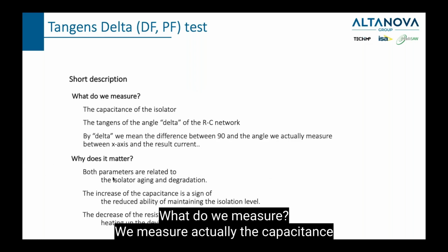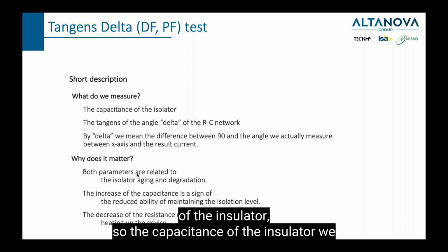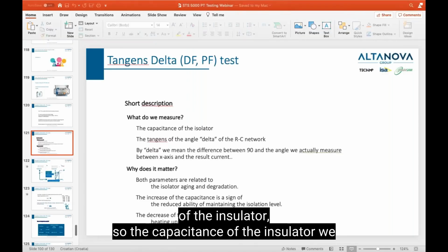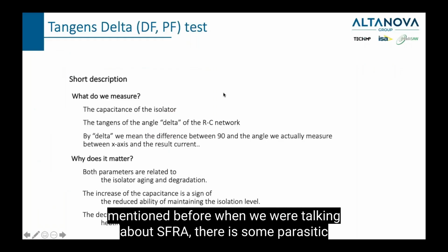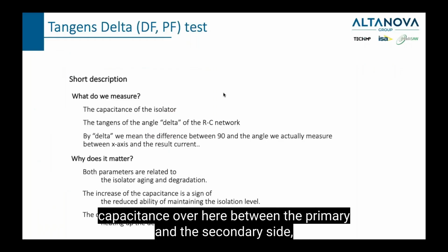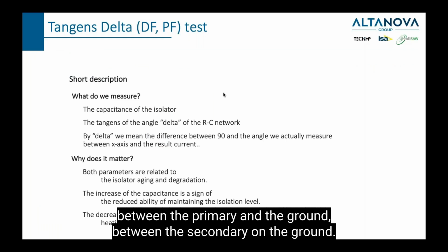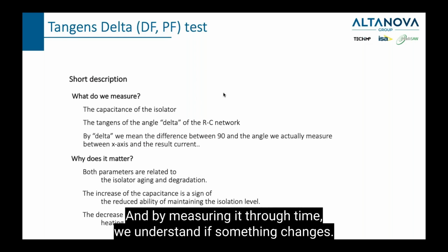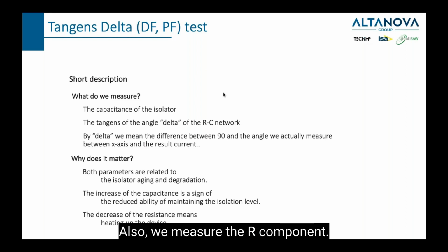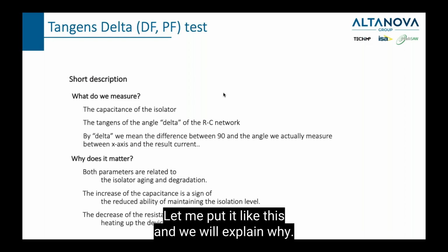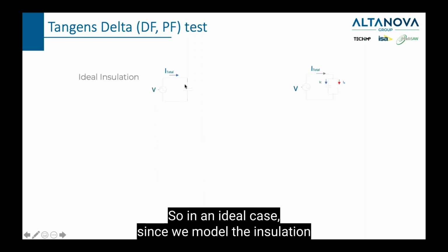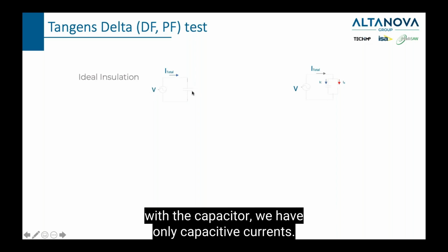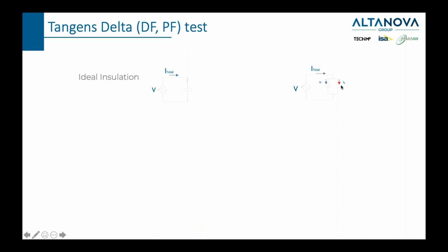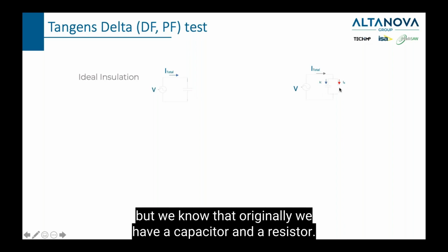What do we measure? We measure actually the capacitance of the insulator. So the capacitance of the insulator we mentioned before when we were talking about SFRA, there is some parasitic capacitance over there between the primary and the secondary side, between the primary and the ground, between the secondary and the ground. And by measuring it through time, we understand if something changes. Also, we measure the R component, let me put it like this, and we will explain why. So in an ideal case, since we model the insulation with the capacitor, we have only capacitive current. As you can see, we have a capacitor here. But we know that originally we have a capacitor and the resistor.